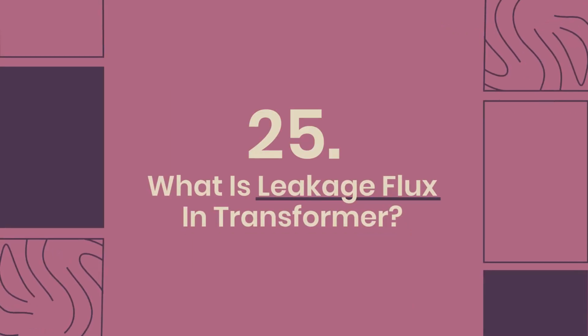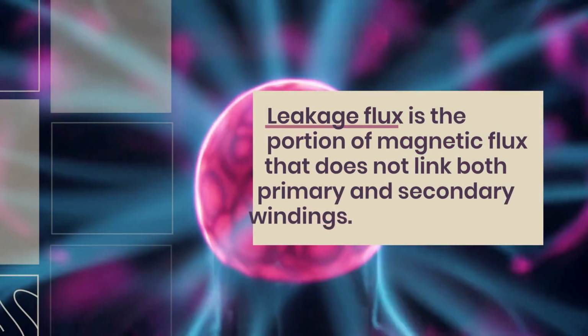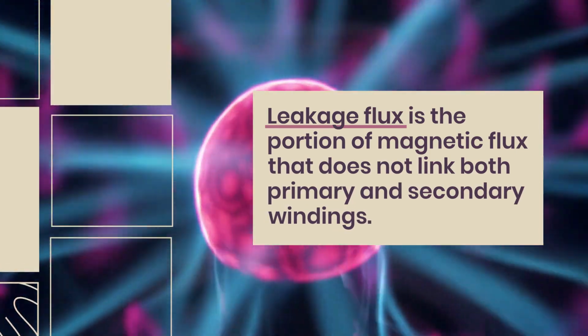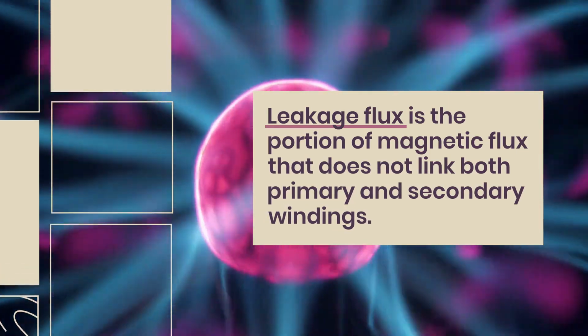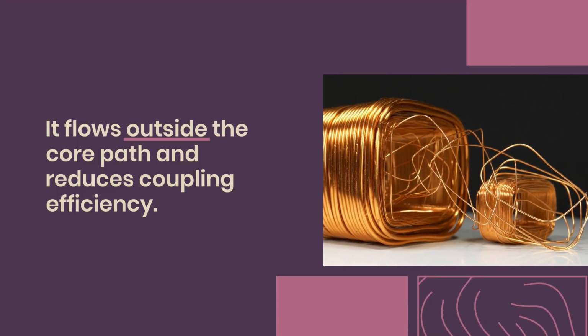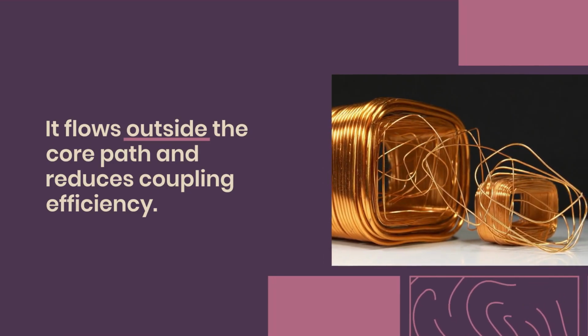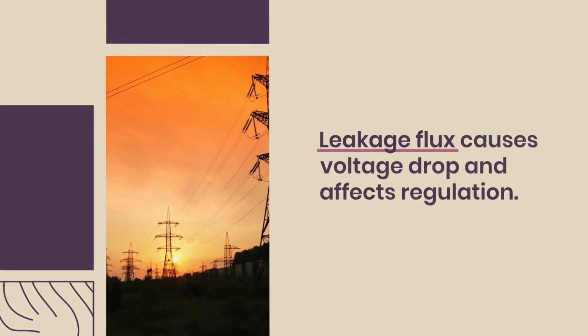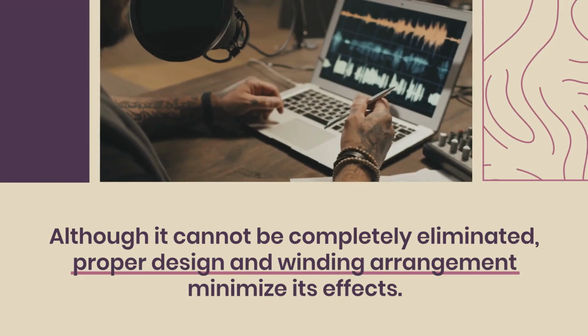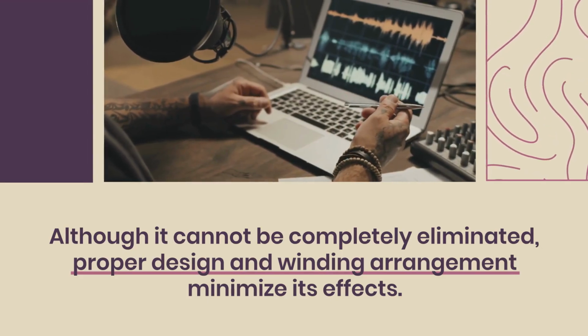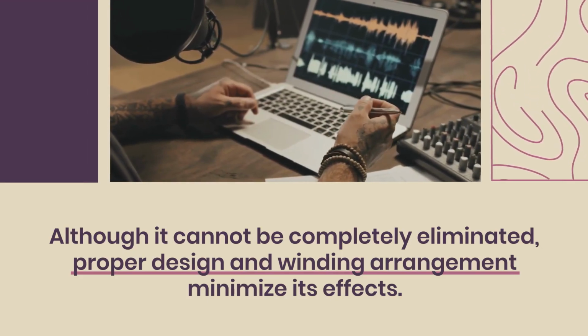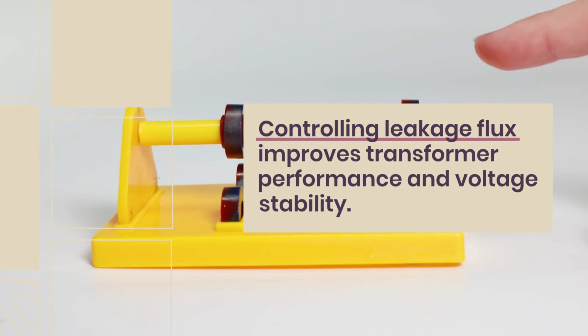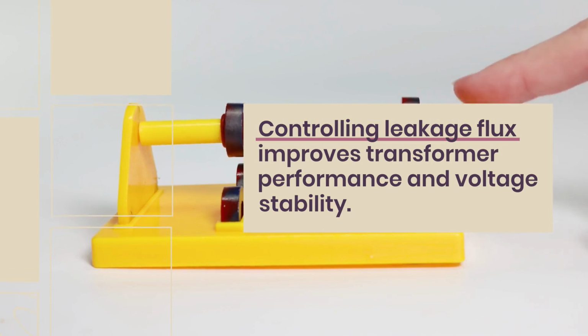25. What is leakage flux in transformer? Leakage flux is the portion of magnetic flux that does not link both primary and secondary windings. It flows outside the core path and reduces coupling efficiency. Leakage flux causes voltage drop and affects regulation. Although it cannot be completely eliminated, proper design and winding arrangement minimize its effects. Controlling leakage flux improves transformer performance and voltage stability.